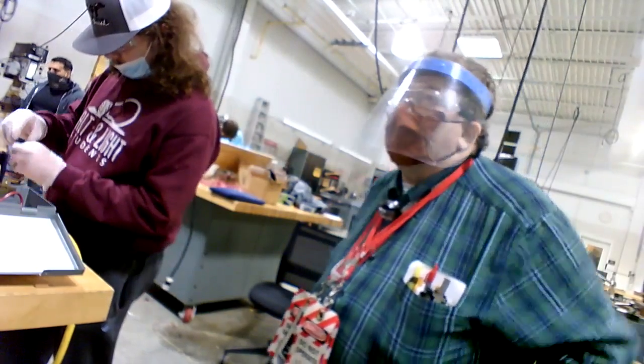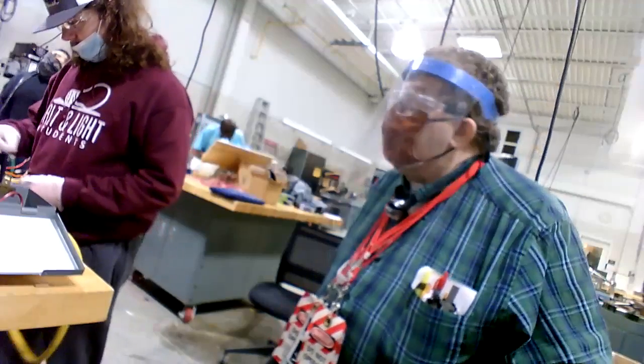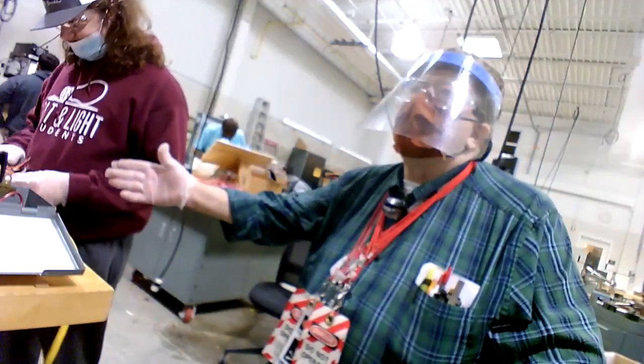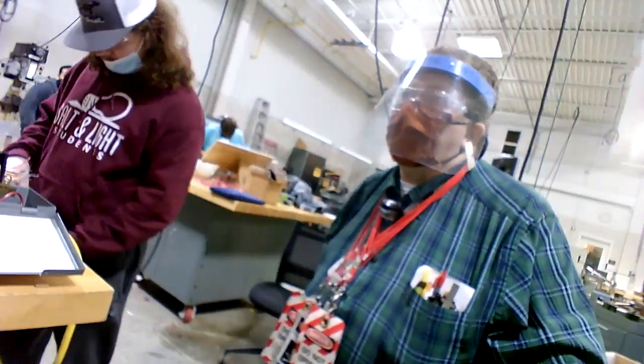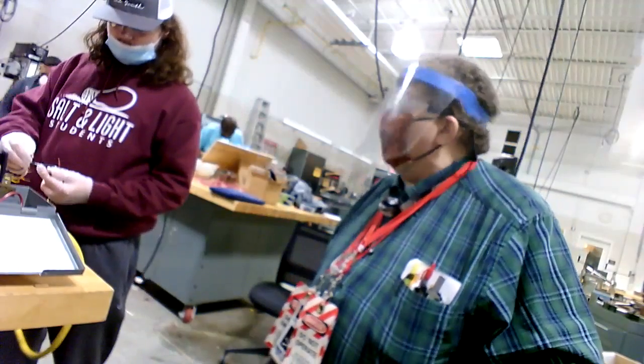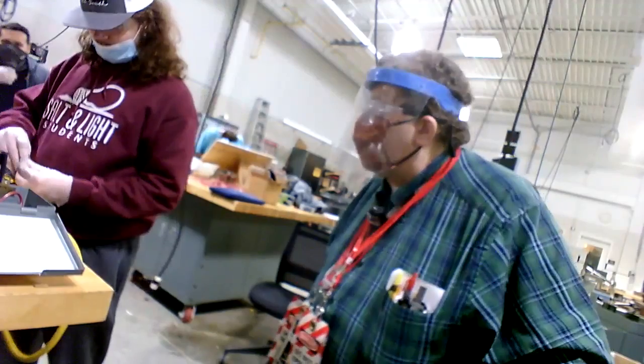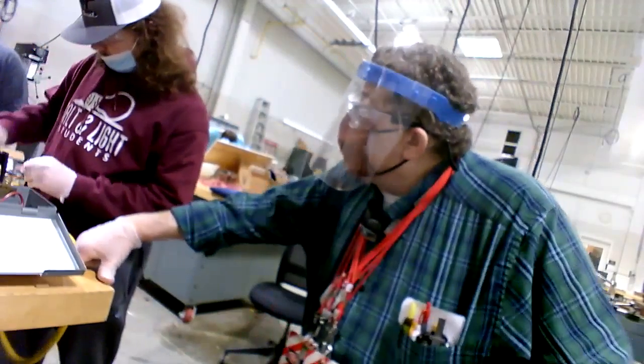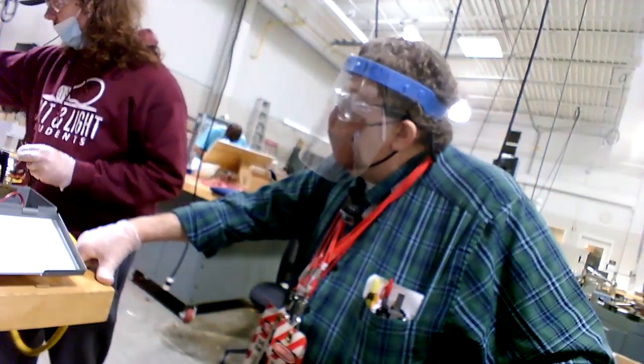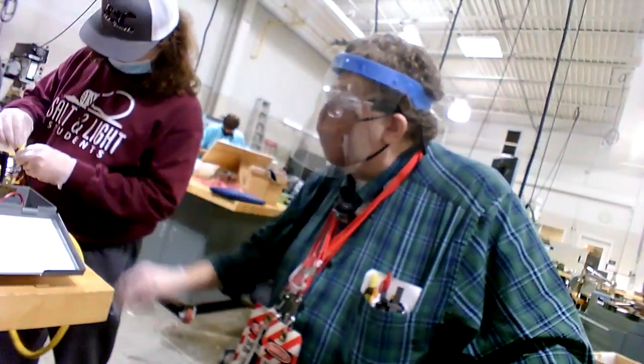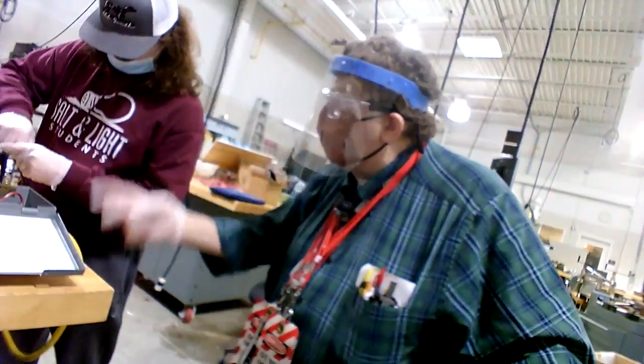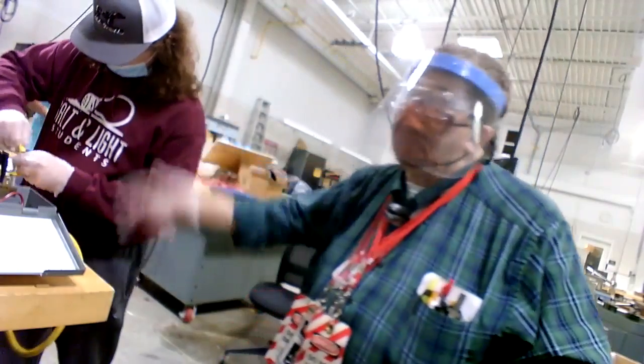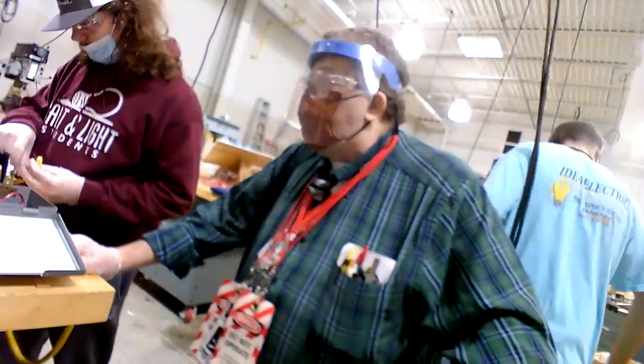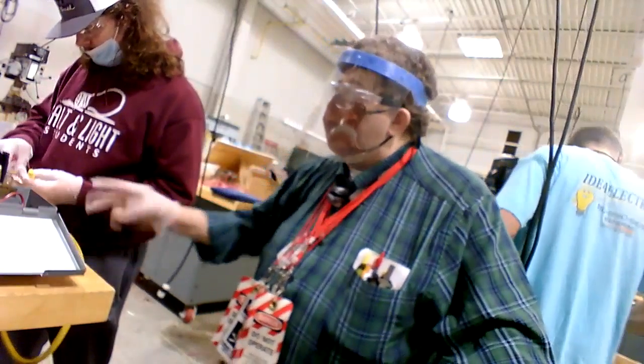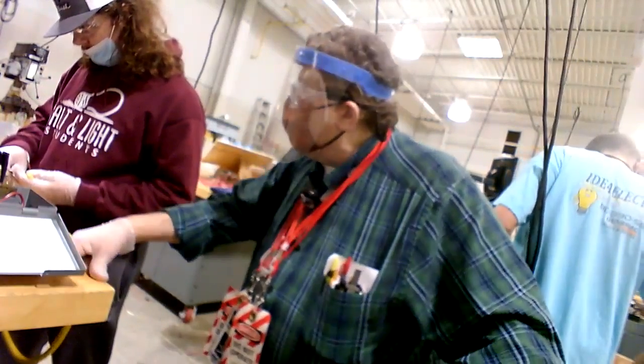They can run on low or high. And then the company doesn't have to stock so many motors, since one motor can go in a lot of places. So either one of these can go to the blue? They can. Yeah. And it won't even change the direction of the motor. The incoming wire is going to that motor. If you flip the power lines going in, that motor still goes clockwise on a single phase. And when you go 3 phase, it changes. When you flip the incoming line, it'll make it go the other way.